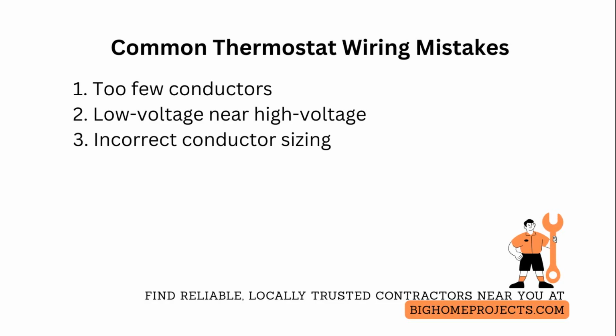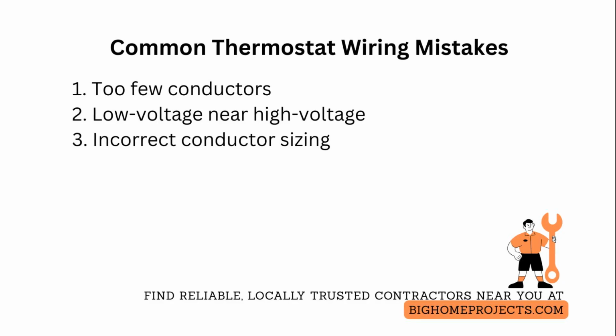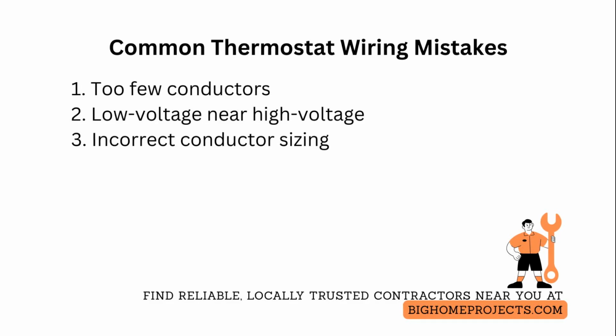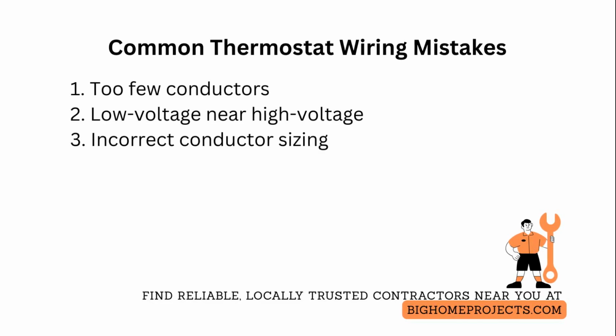One of the next common issues is running low voltage cable alongside high voltage mains, which creates noise and intermittent control faults. Resolve it by rerouting cable, maintaining a 6-inch separation, or crossing at right angles and using shielded cable if necessary.